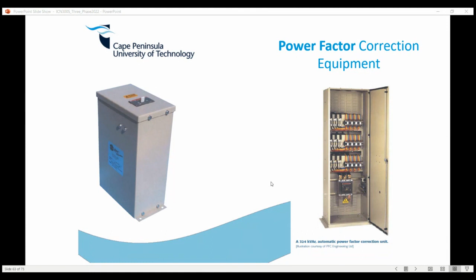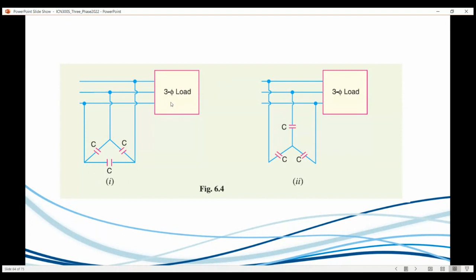Yeah, so what you're seeing over here is a device called an automatic power factor correction unit, which can be coupled to where the generators are, and it corrects the power factor automatically if it gets poor. There's a bunch of capacitor banks here, and if the power factor goes below a certain threshold, then this will kick in. So this is just an example of what I was referring to on the slide, of what it would typically look like. We typically connect it in delta, and the capacitor bank will be configured like that to the load in this case over here.